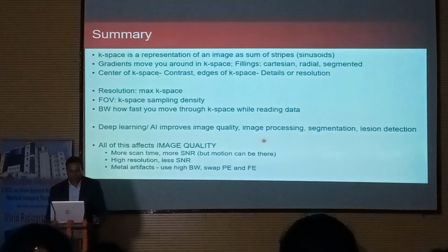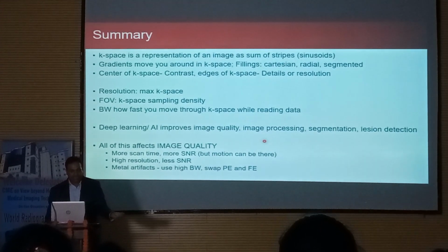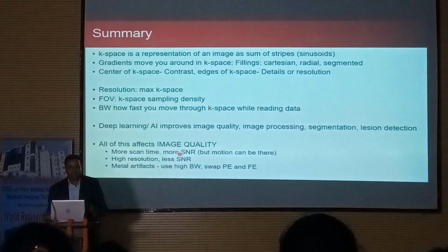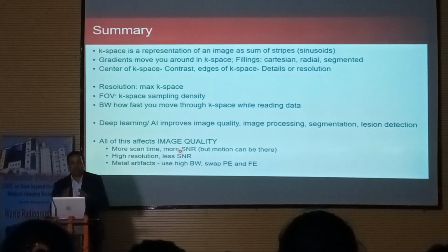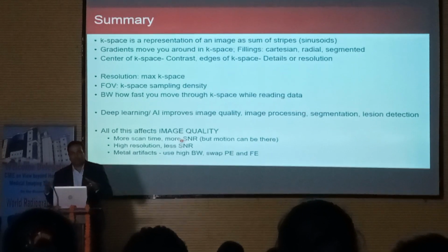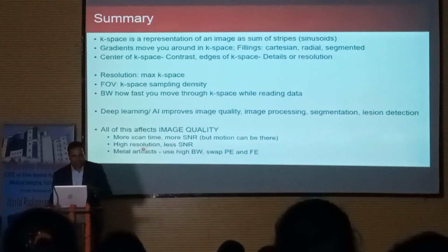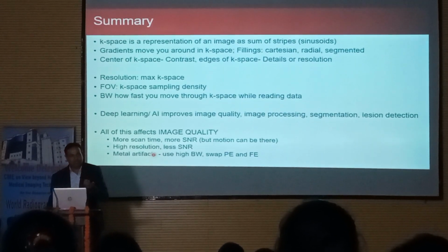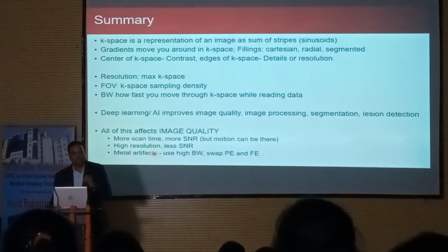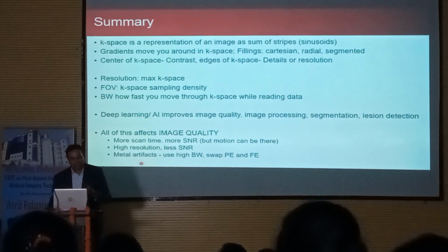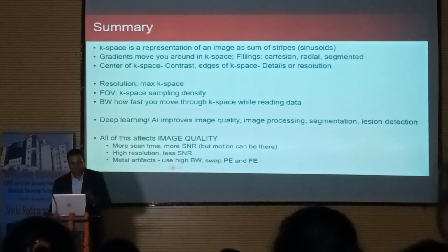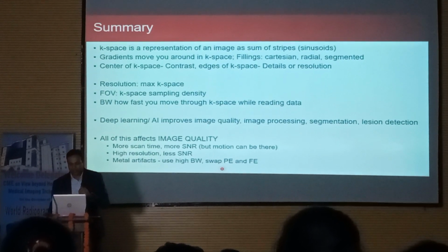Lastly, all of these affect image quality. More scan time will give more SNR, but at the same time our image might have motion artifacts because you kept the patient inside for a longer time. If you want higher resolution, then you will have to deal with less SNR. Metal artifacts can be dealt with by using high bandwidth or swapping frequency encoding with phase encoding.